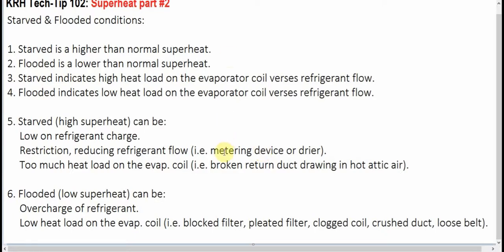If you look at the metering device and notice that it is frosted on one side, and this is regarding air conditioning, not refrigeration, then that means that on one side of the metering device, the boiling point is higher than 32 degrees on the inlet, and on the outlet going to the coil, it's lower than 32 degrees. Now this would indicate that the metering device is restricting. That's normal operation for that metering device. But if your dryer is not indicating a temperature drop, my primary pressure drop is happening at the metering device.